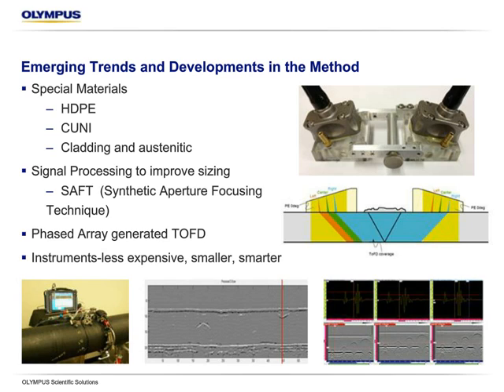Phased array generated TOFD. So here on the right-hand side all the way down, we have phased array transducers that were designed to do all three different setups of TOFD that we would use in corrosion and erosion all at once, and be able to display that in a very familiar format, 3 TOFD displays, and just give us a good ability to do it very accurately, positioning the phased array transducers.